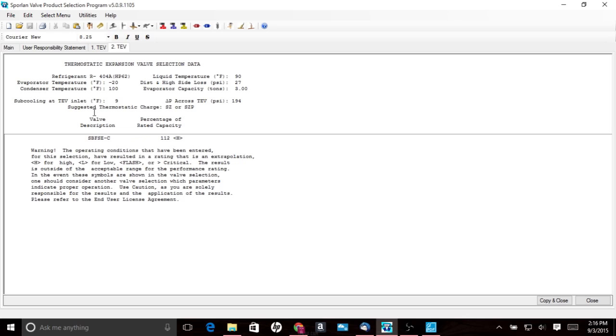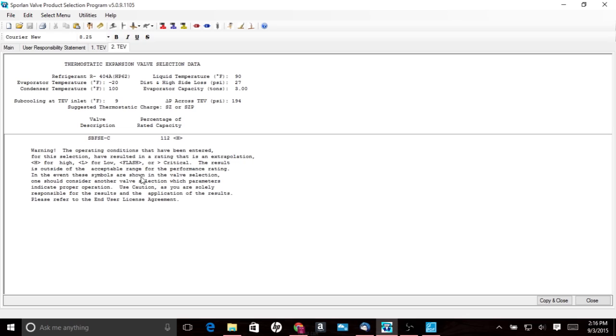So it tells you our subcooling is 9 and minus 20 evap temp, 100 degree condensing temperature. And we're rated 112. So it's going to give you this warning here that says, you know, warning, you have something going on with your valve and it's not going to work right. So we see obviously the H is for high. And you can tell that the valve is undersized at that point.